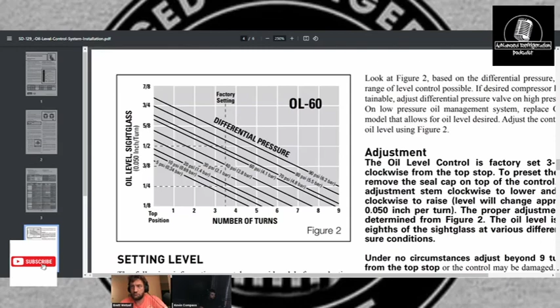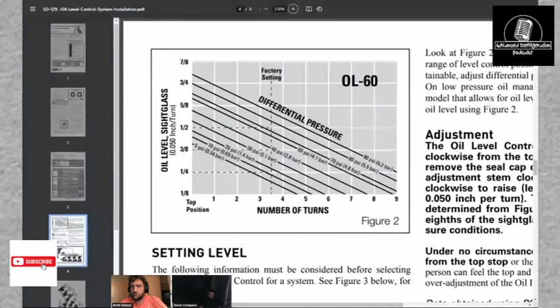That's the way that these floats work. And then all you're doing is setting that stem in there to work off a differential, and then that's setting your level. As the float ball drops, it's going to allow oil to come in, and as it rises, it's going to pinch off and seal off the float. Now, these floats do have a screen in them. Not every float has an inlet screen. The Henry ones, I don't believe, do. The Sporlan ones do have an inlet screen that can clog up and get dirty. Yep. You don't see those dirty that often. Usually by then it's already in the oil filter.